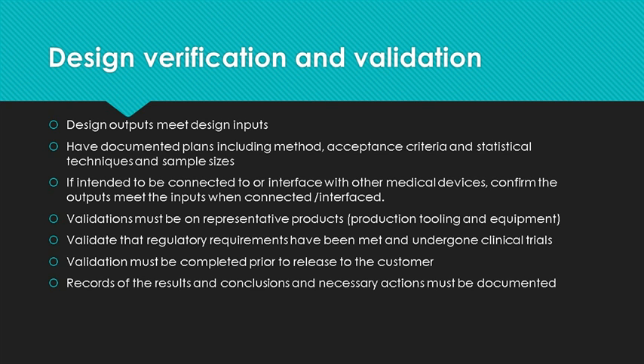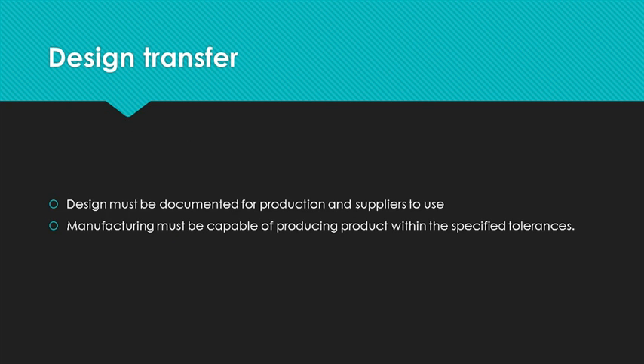Now, once the design is verified and validated, the design process is not complete. The design must be documented for the transfer to manufacturer and the suppliers. This is the generation of drawings, specifications, production plans, test methods. The design team is responsible to confirm production is capable of producing the product to specifications and within tolerances. If not, they must work with production until the production is capable.